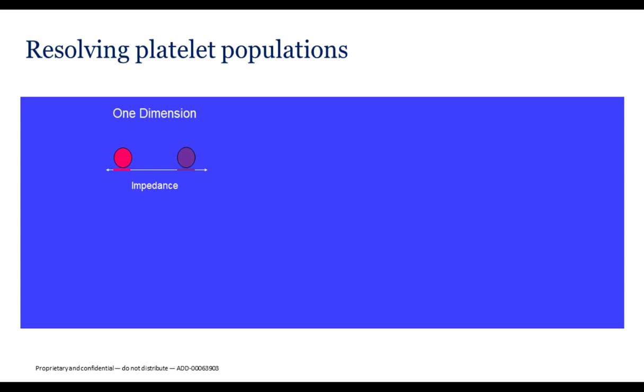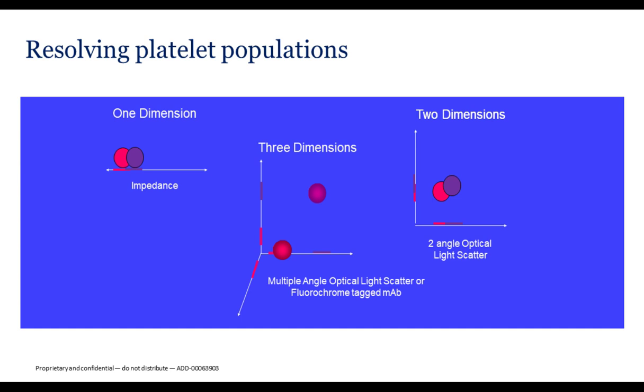To summarize resolving platelet populations: the one-dimensional approach (impedance) separates cells of similar size only, and overlap can occur. The two-dimensional approach using two-angle optical light scatter provides clearer separation, though overlap can still occur in some instances. The three-dimensional approach — multiple-angle optical light scatter or fluorochrome-tagged monoclonal antibody — provides the most definitive separation; even when interferences or similarities exist, the fluorochrome-tagged monoclonal antibody will ultimately separate the platelet population.